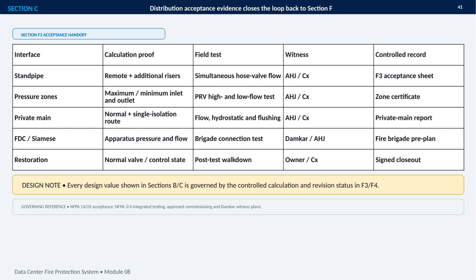Pressure zones require maximum and minimum inlet and outlet calculations, followed by high and low flow testing of the pressure-reducing valves. The private main is checked for both normal and single isolation routing, along with flow, hydrostatic, and flushing tests. For the FDC or Siamese connection, the team verifies apparatus pressure and flow, then performs a brigade connection test. Finally, restoration confirms that valves and controls return to their normal state, supported by a post-test walkdown and signed closeout.